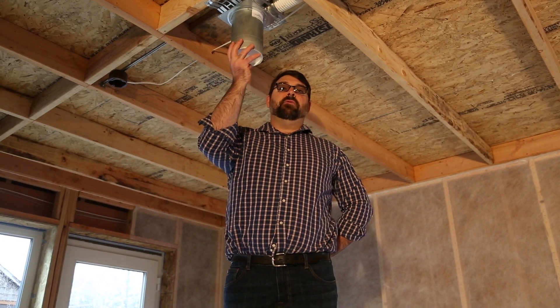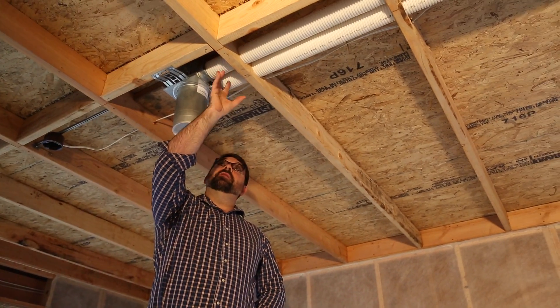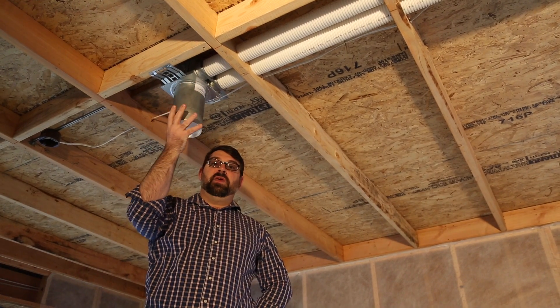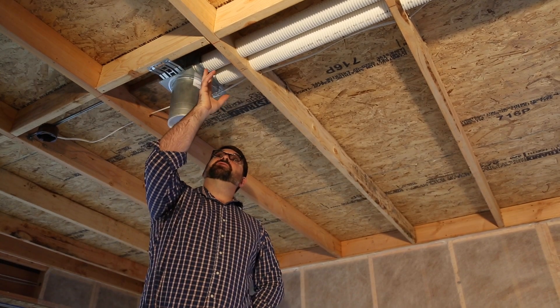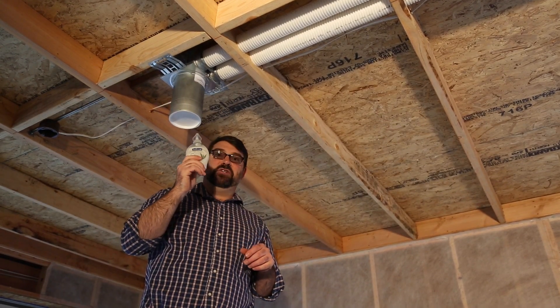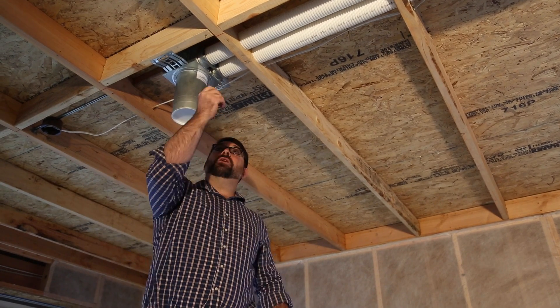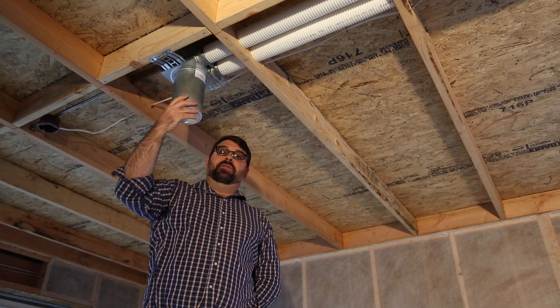The Zehnder heat recovery ventilator utilizes the Comfo Tubes, and in this particular room the ventilation demands called for two tubes to this register. Those tubes slide into the manifold with a little special lubrication and are then clipped into place to maintain the air seal.